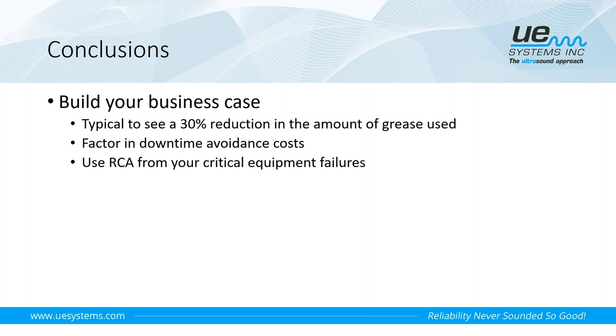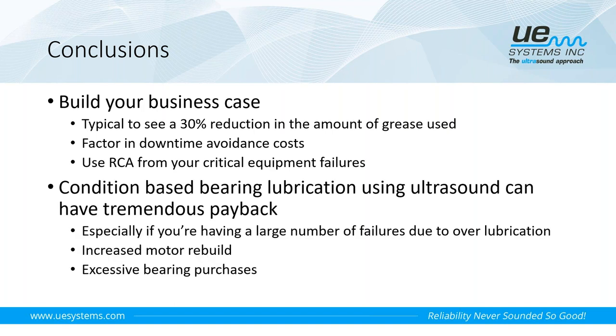Be sure to factor in any downtime avoidance costs. If you're doing root cause analysis on some of your more critical equipment, use that information to help you build the business case for this. If you're having failures due to over lubrication, if you are sending a lot of motors out for rebuild, where when they break into those motors they're seeing grease in places where it shouldn't be, you can have some significant savings initially, not only from the reduction in the amount of grease being used, but if we have fewer motors being sent out to be rebuilt, if we have fewer bearing failures, it's really going to add up.